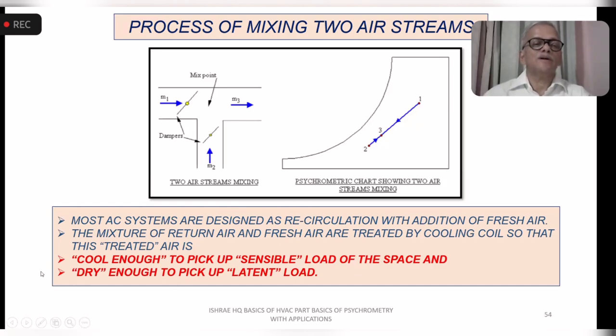The tolerances, plus minus, are generally for the control system's performance. Then the air has to be dry enough to pick up the latent load. So you must make sure that your supply air conditions are right to meet the space loads, sensible and latent, ideally for all the spaces, since you have a common air handling unit.